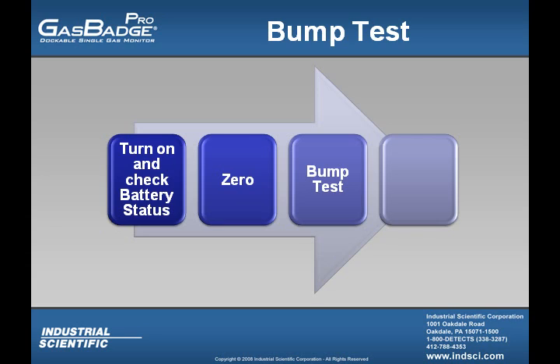The third step of operation is to perform the functional test, also known as the bump test. A bump test is defined as a brief exposure to a known concentration of gas, making sure that the instrument goes into alarm. During the bump test, you want to make sure that you feel the vibration, see the visual alarm, as well as hear the audible alarm. I look at the bump test as a confidence booster for yourself, to know that when you're in an atmosphere and there's some bad gas, your instrument will without a doubt go into alarm, letting you know that you need to get out of that area.